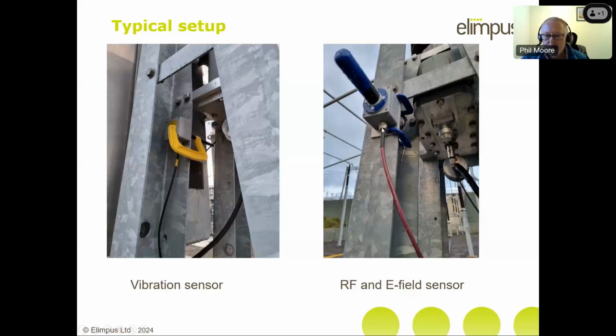A similar comment applies to the RF and the E-field sensor. This is basically a monopole antenna, which we try to put as high up on the structure as possible so that it gives the best measurement of the E field. It doesn't really make much difference for the RF, but the E field benefits from being higher up on the structure, and not so high up that you need to work from height or switch anything off. Just as high as you can get it without any safety or system implications.